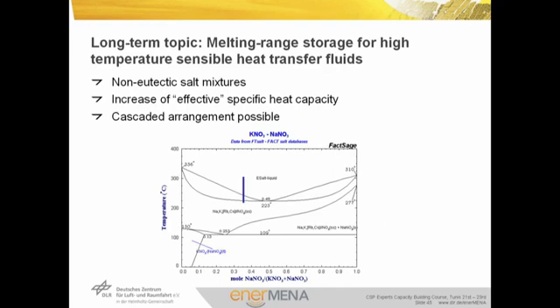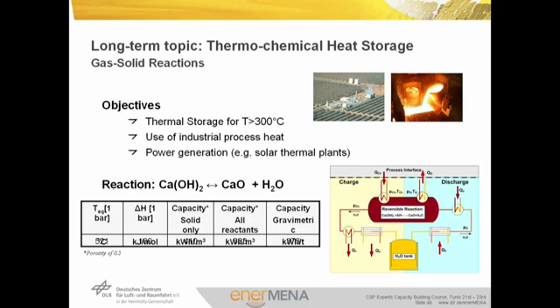Another storage concept under development is the use of non-eutectic salt mixtures as storage material. Here, the phase transition takes place over a wider temperature range. Within this temperature range, the effective specific heat capacity is higher than for other sensible storage media. Systems of non-eutectic storage materials can be cascaded to extend the operation temperature range. Another approach for storage of thermal energy is the use of reversible chemical reactions, for which a high volumetric storage density is expected.